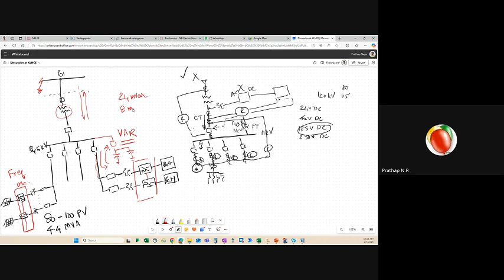The other option before this would be to switch in a capacitor bank. So during daytime, when the grid is overloaded and reactive power support is needed, you need capacitor banks to be switched on. Capacitor banks are usually huge. And then you may need to stage them. Let's say you have a 24 MVAR cap bank. If you add the 24 MVAR cap bank, that's one stage. And if you don't want that, you need to break them into, I've seen 2, maybe 3 stages, like 8 MVAR, but the controls become very complex in that case.